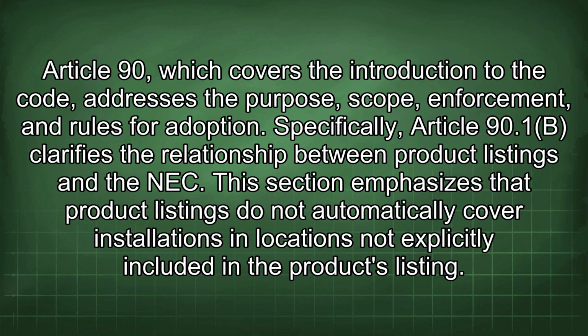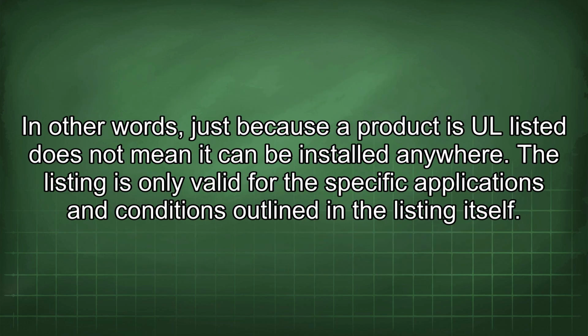Article 90, which covers the introduction to the code, addresses the purpose, scope, enforcement, and rules for adoption. Specifically, Article 90.1b clarifies the relationship between product listings and the NEC. This section emphasizes that product listings do not automatically cover installations in locations not explicitly included in the product's listing. In other words, just because a product is UL listed does not mean it can be installed anywhere. The listing is only valid for the specific applications and conditions outlined in the listing itself.